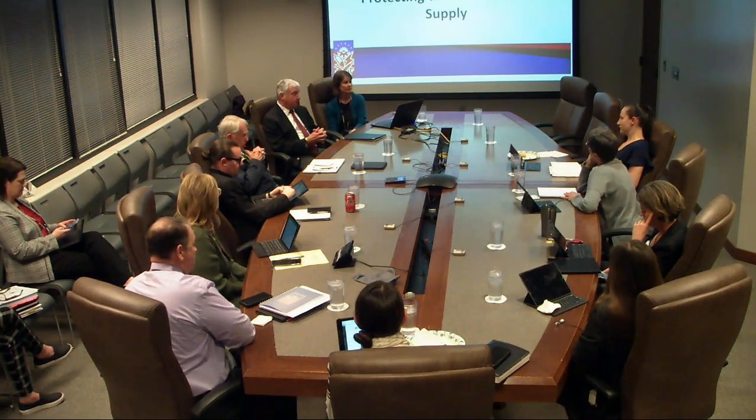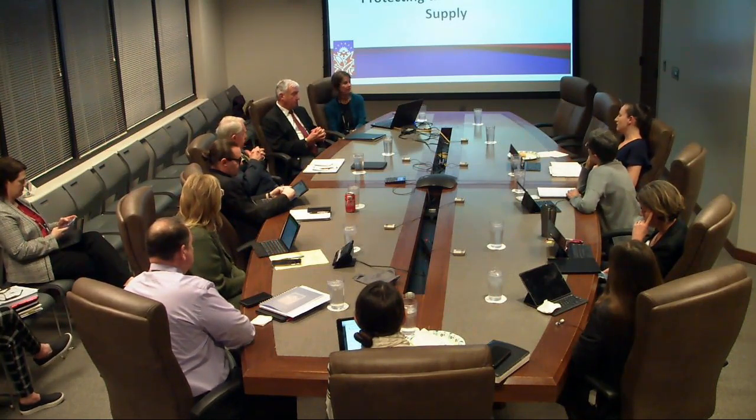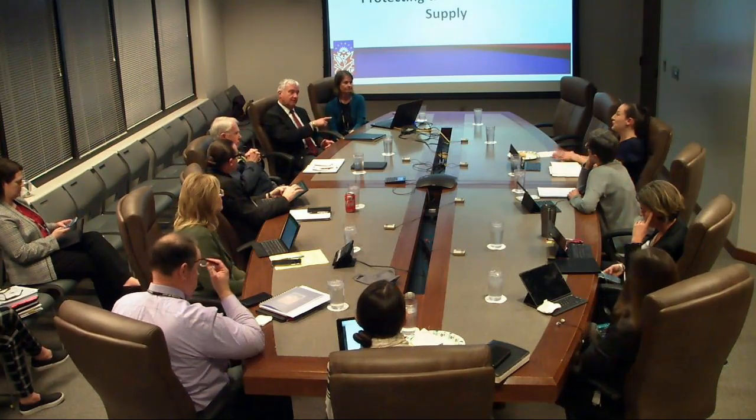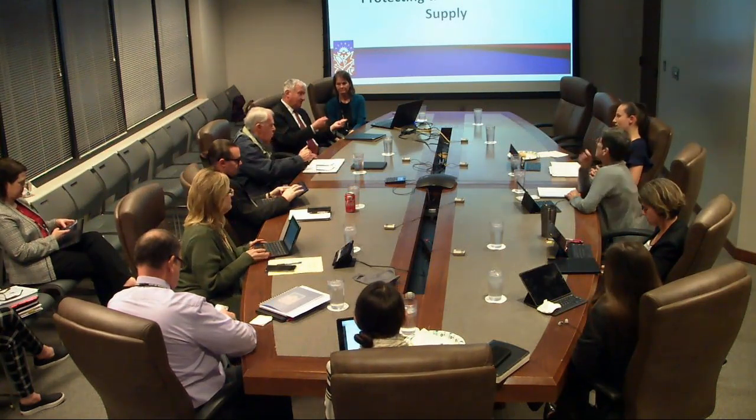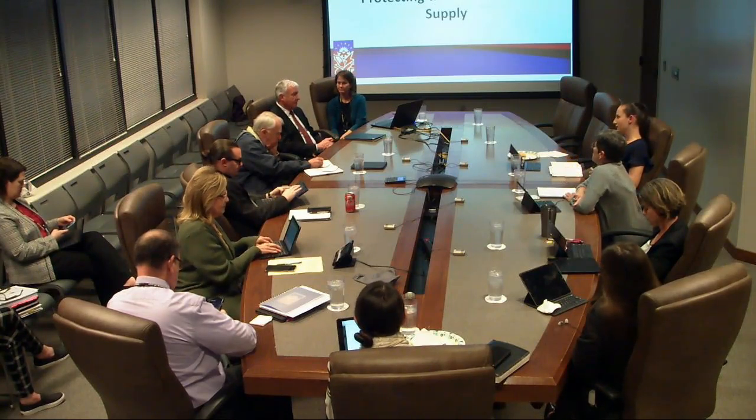Yes, we would like very much to use utility bills, our website and other methods of educating the community before we impact any residents, for sure. But realistically, it'll be years before we get to that point. We should make that clear. I don't want to unnecessarily concern people too early when we start talking about this. We want to make sure we get the hospitals, the mortuaries, the dentist's offices, the car washes, things that are pressurizing their system. We don't want them pushing stuff back into our system. If everybody gets an irrigation system, it should come with a vacuum breaker, and that should be good enough. We'll worry about that later.